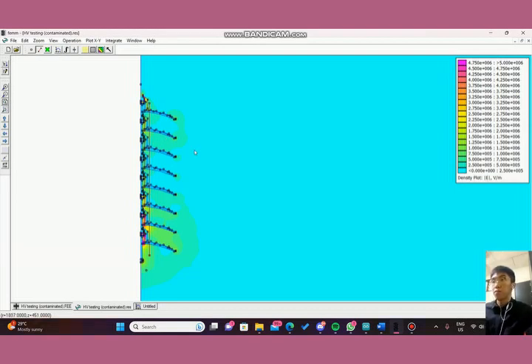So the contaminant conditions create sharper edges from the dust, and uneven inclining lines as compared to the clean conditions. This is because the accumulated dust on the surface of the glass plate creates more uneven points, which slightly changes the structure of the insulator. The uneven points affect the distribution of the E field, the electric field, as the electrical charge has more tendency to appear towards the sharp points. Hence, the field strength increases at particular points, like this one and this one.